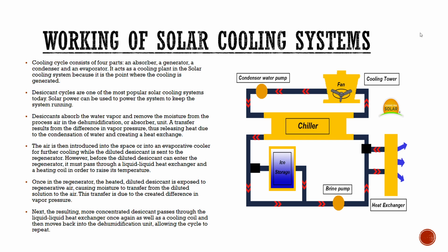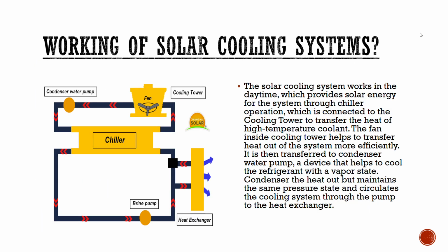Once the regenerator is heated, diluted desiccant is exposed to regenerative air, causing moisture to transfer from the diluted solution into the air. This transfer is due to the created difference in the vapor pressure. Next, the resulting more concentrated desiccant passes through the liquid to liquid heat exchanger once again, as well as a cooling coil, to then move back into the dehumidification unit, allowing the cycle to repeat. So this is the working of solar cooling power system during the day.